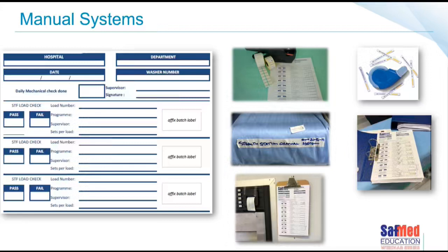Right, so the whole idea, of course, is that we can track each set and instrument back to the actual autoclave itself. And at the end of the day, hopefully we have the ability to track which patient these devices were used on. Or, in what autoclave did the instruments that were used on this patient get sterilized? Was the autoclave working? There is your evidence. Of course, the disadvantage of the system is you're only recording the data at one point of the sterilization, or instrument reprocessing, system. You're only recording one point of it, but at least it's one point, which of course is better than nothing.